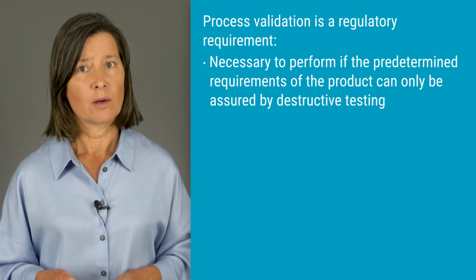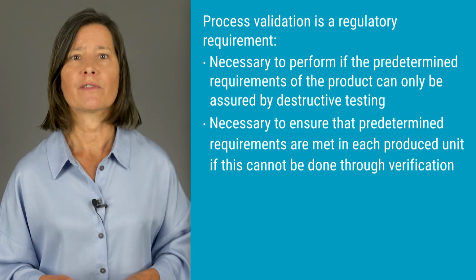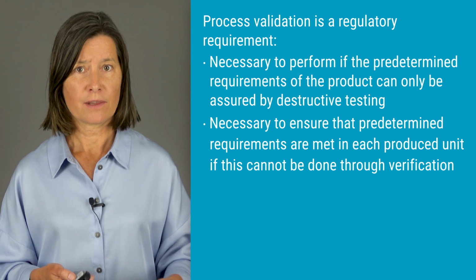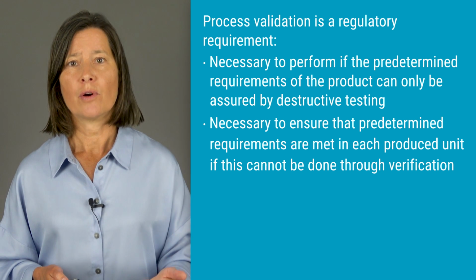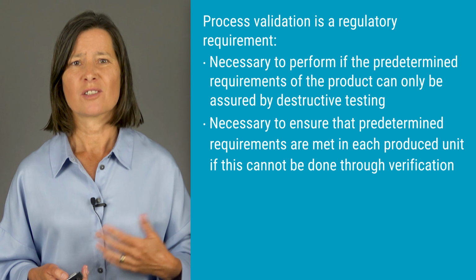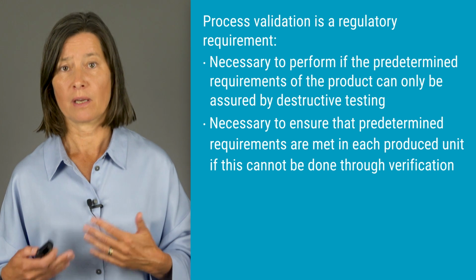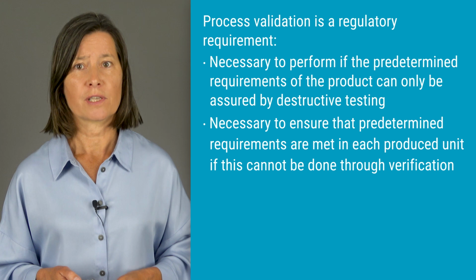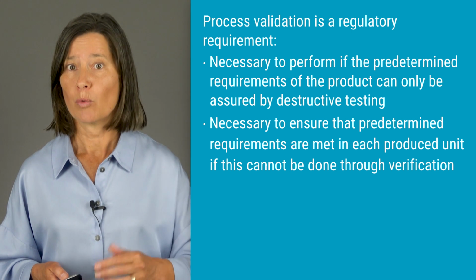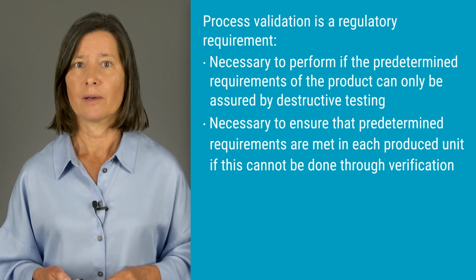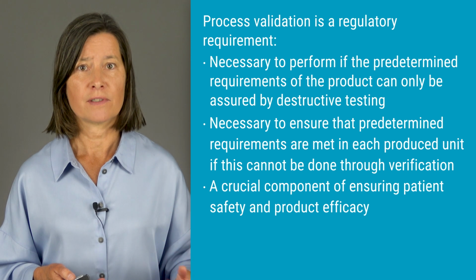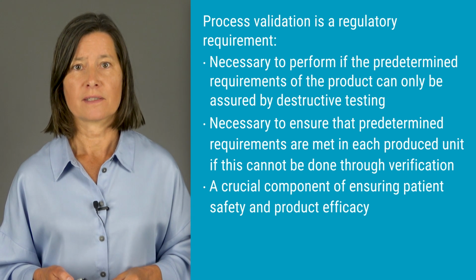In some cases, we could perform 100% verification on all products, for example, measuring the weight or the length of the part. However, we may choose not to, as it's too cumbersome, too time-consuming, and too costly. If these measurements are critical for the safety of the device, then we need to perform process validation as well. And again, the aim is to ensure patient safety as well as product efficacy.